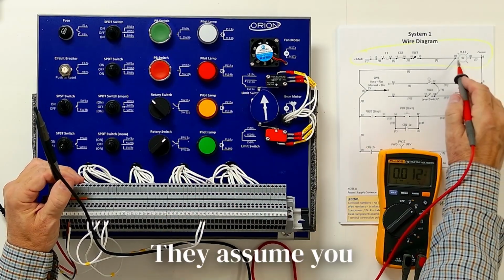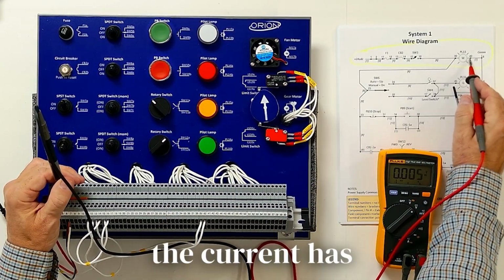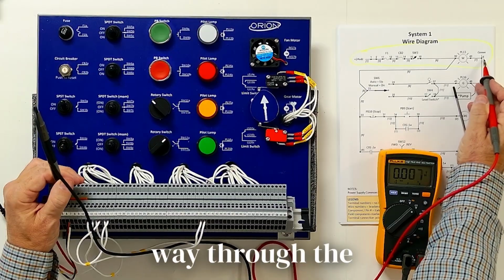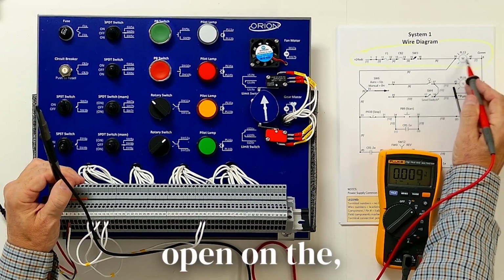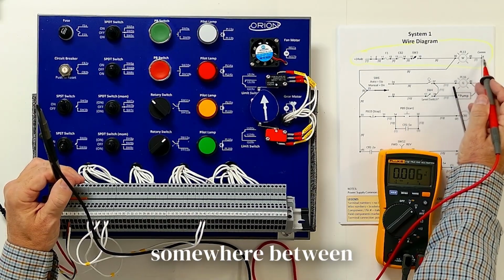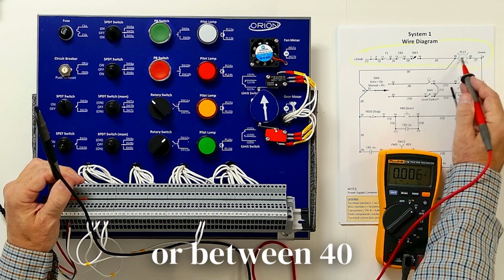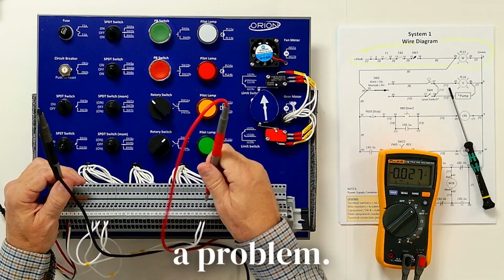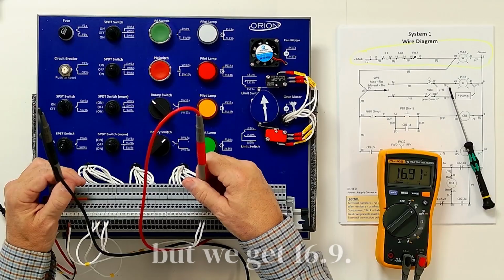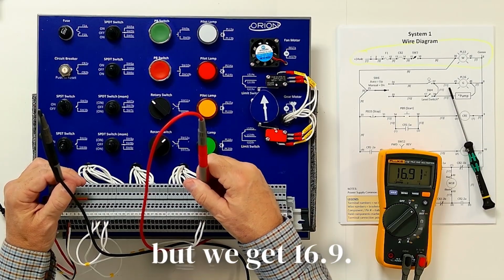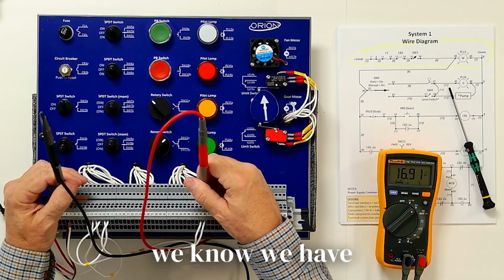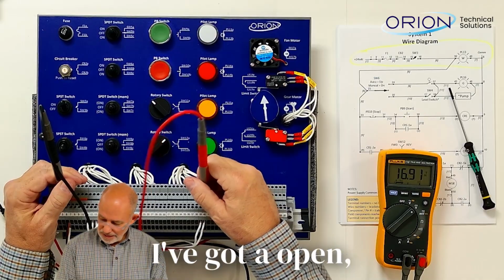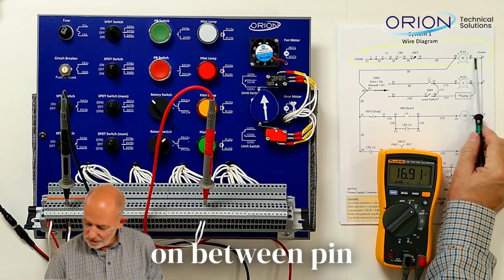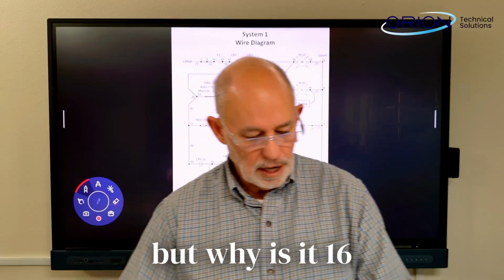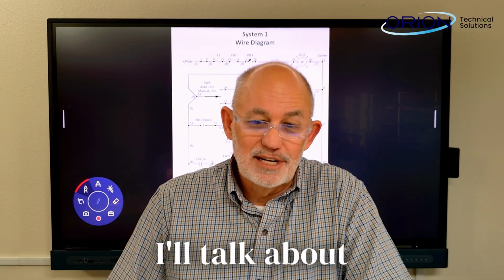Well, terminal block 40, people forget to check. They assume if you've got power to the device, it works. They always forget that current has to flow all the way through the circuit. Well, if there's an open on the common, somewhere between, say, 6 and 40, or between 40 and the light, that will cause a problem. Now, we should get 0 volts there, but we get 16.9. If it's not 0, we know we have a problem. So that tells me I've got an open something going on between pin 6 and 40. But why is it 16 volts? Well, I'll talk about that in just a second.